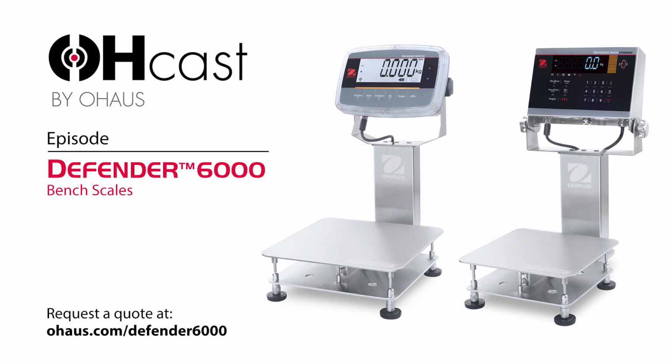In the switch from the Champ to the Defender, did you address anything in particular that maybe came out of the customer experience? Were there things that customers were looking for that maybe weren't there in the Champ that are now in the Defender? One thing that customers were looking for was more options in terms of data connections. So RS-232 is a standard that you find throughout weighing equipment in the industrial area. Even though it's a very old standard, it's a very common standard. But they also were looking for things like Ethernet, USB connections, even old technology like analog loops, voltage, or current loops. And then also they're asking for new ways to connect, like Wi-Fi or Bluetooth. So those were all brought together in our Defender 5000 series.